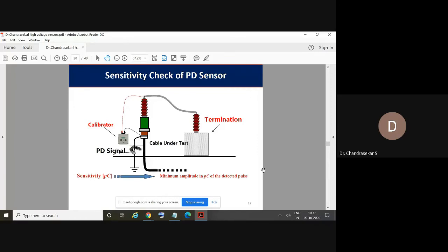Then only we came to know that we didn't measure PD signals; we really measured the radio frequency signal of that particular frequency in our PD system. That's why, at those particular times, we got continuous signals, and those signals were not PD signals. So measuring PD at very high frequency, in fact any high frequency signal measurement, is really very tough, because there are so many radio frequency interferences and noises in and around the environment. Even a cell phone call or any cell phone signal while performing these measurements will give you some disturbance or noise.